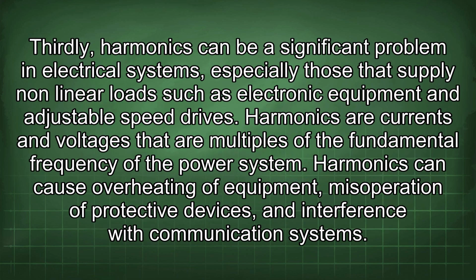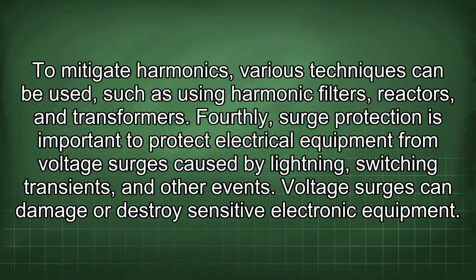Thirdly, harmonics can be a significant problem in electrical systems, especially those that supply nonlinear loads such as electronic equipment and adjustable speed drives. Harmonics are currents and voltages that are multiples of the fundamental frequency of the power system. Harmonics can cause overheating of equipment, misoperation of protective devices, and interference with communication systems. To mitigate harmonics, various techniques can be used, such as using harmonic filters, reactors, and transformers.